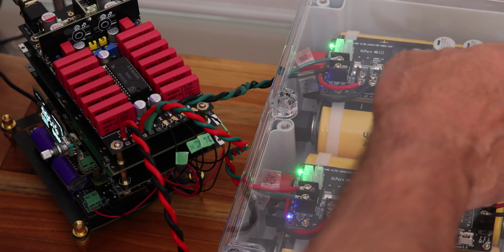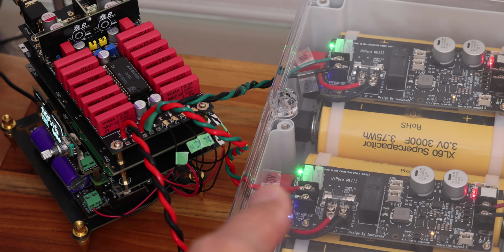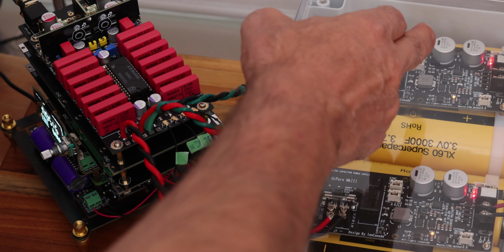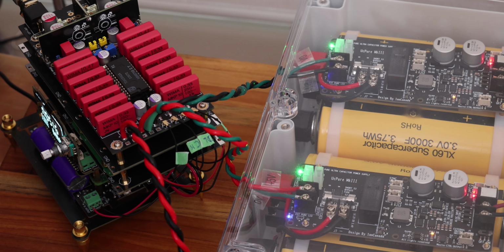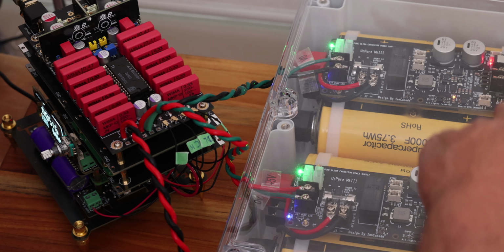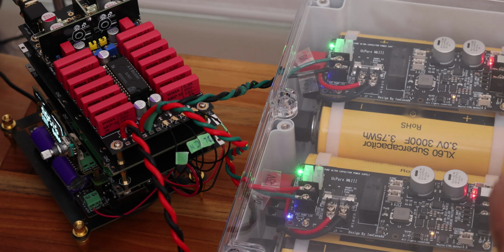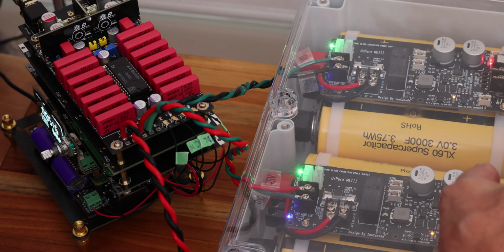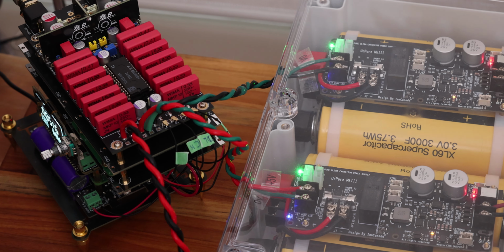The reason you want fuses on these is because a lot of times you have transformers that can handle, for example, 4 amps here and 4 amps here, but the actual line could produce 8 amps, and the wiring in the coil is not made for 8 amps. So that's why they usually want you to parallel them together to be safe. But since we are splitting them, that puts you in danger of actually burning the coil on the transformer if something shorts here. So it's important to have at least a 4 amp fuse on each one of the lines. What the coil is rated for decides how big a fuse you should put on each line. It could be 2 amps, could be 4 amps. Just check your transformer and how much you should put in. Because we're going to use about 3 amps, usually a 3 amp fuse is probably the maximum you want to put in.